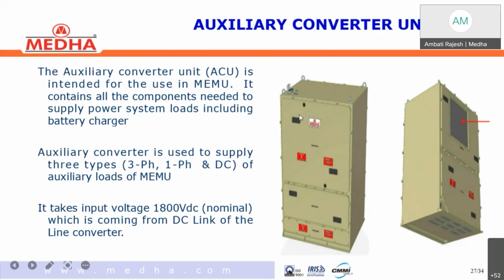This is a 120 kVA rating converter. If all the auxiliary converters in the individual basic units are healthy, then the changeover contactors will be in the open state. Each auxiliary converter provides these three low voltage supplies to only 4 coaches, and normally it works like that. But while the train is working, redundancy is provided via the 110 volts changeover contactors and 415 volts changeover contactors. In case this aux converter is declared faulty in a basic unit, the adjacent basic unit aux converter supply comes to this basic unit. For that purpose, the internal changeover contactors will be energized by the TCMS automatic system, based on the fault status of this aux converter, and the system energizes the changeover contactors between two basic units and gets the auxiliary supply from the adjacent basic unit.